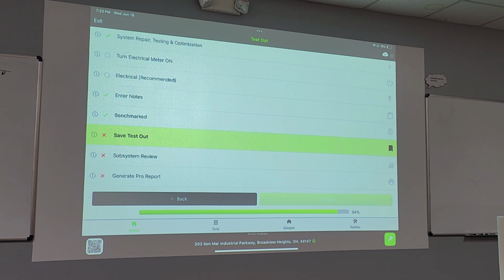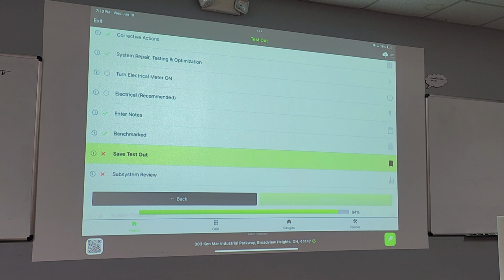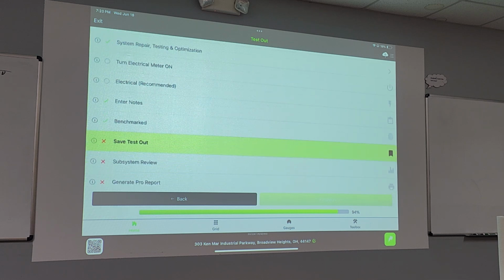So now it's saying this is kind of normal for this unit, and I can save my test-out snapshot of measurements. At this point, I should have corrected the refrigerant charge before benchmarking, and before testing out, everything should be set as I'm going to leave it.